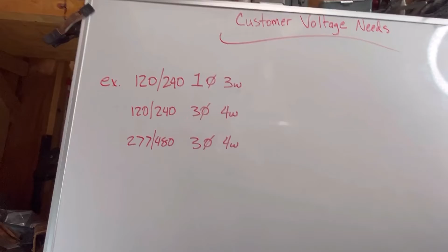So those 3 wires made up of 2 phases and a neutral, 120/240 single phase 3-wire. Another way they could tell you, they might say, I need 120/240 3-phase 4-wire. 4 wires being 3 phases and a neutral. The 4th wire is always the neutral. Or maybe it says 277/480 3-phase 4-wire. Again, being 3 phases and a neutral, right? So what in the world does all that mean, and how do we use this information to determine a secondary hookup?